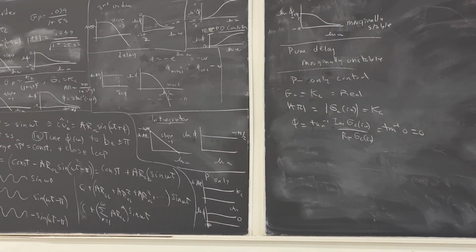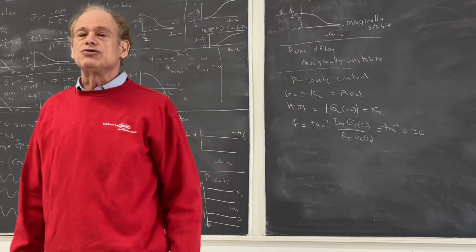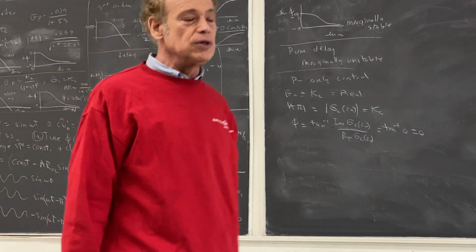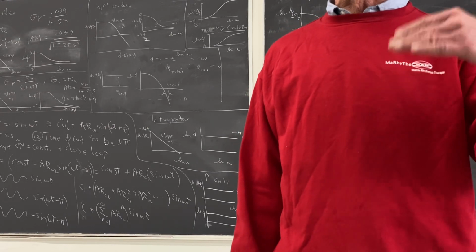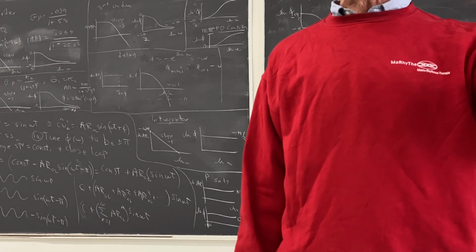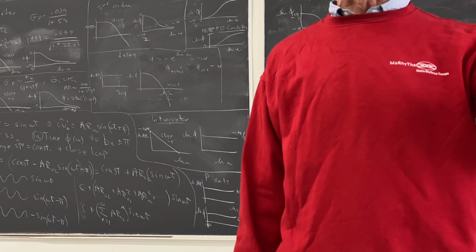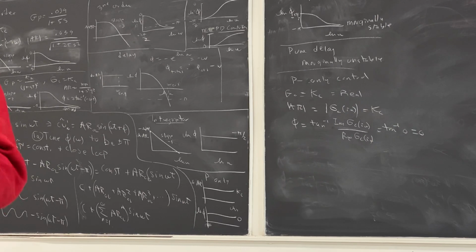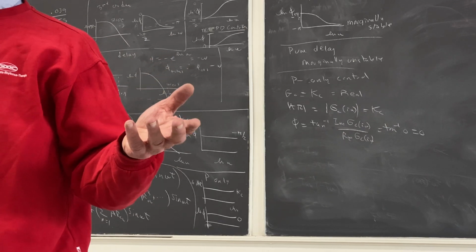Okay, as I mentioned in the overall intro about 15 minutes ago, when we introduced the PID controller, we noted that there were 3 parameters that we had to tune: Kc, TI, TD. We want to tune them so that if there's a disturbance or change in the set point, we go fairly quickly back to the set point we want, but not so quickly that the system blows up and it becomes unstable. So obviously if it takes forever to get there, it's not going to be unstable, but it's not desirable. If you make the controller too aggressive, then you think you're going to get there, but you overshoot, and then the system blows up.